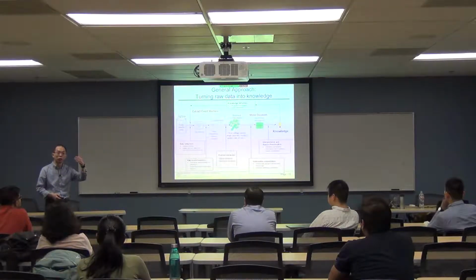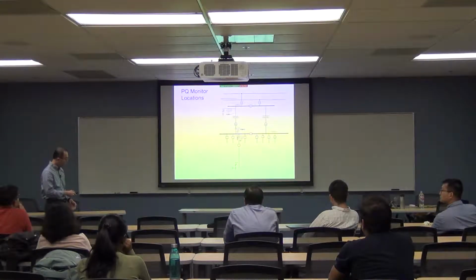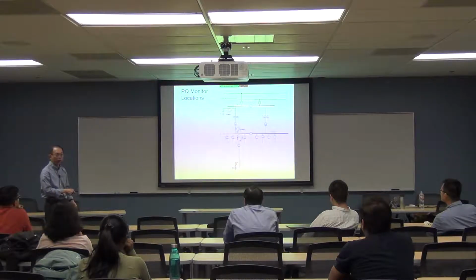It means the first thing to do is develop an algorithm to detect capacitor energizing. Suppose your power quality monitors are located at the feeder head—this feeder head monitor will see all kinds of disturbances, so you have to remove all of them and keep only those related to capacitor switching.